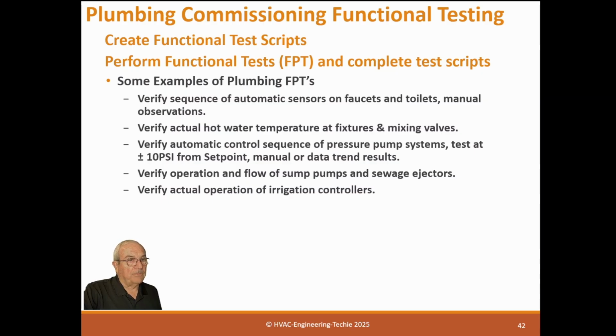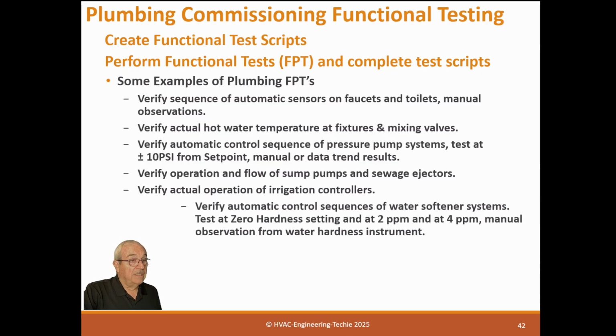Verify actual operation of irrigation controllers. Make sure the control timers work and are on the right amount of time. Verify automatic control sequences of water softener systems. Test at 0 hardness, test at 2 ppm and 4 ppm, with manual observation from a water hardness measurement. So that's still another manual functional test.